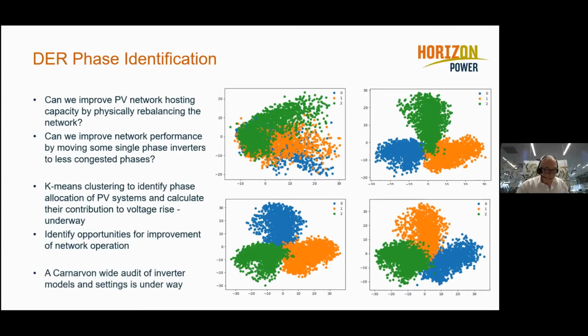Now, what we've observed through these trials is that of the 82 inverters that we are monitoring, more than 50% are not working as well as they could, which is unsatisfactory for both the customer and the network operator. Loss of PV generation is a loss of income or saving for the customer, while frequent inverter trips due to high voltage exacerbate the fluctuation factor of the renewable energy generation that is manifested to the network and ultimately to the power station, and thus that reduces hosting capacity.